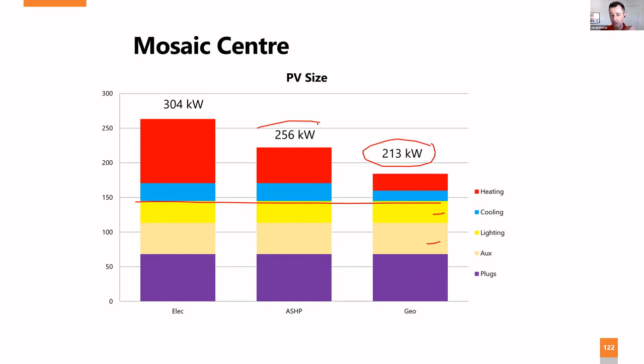And the cost of that solar PV is different. So even though the cost of the geo system was an $80,000 premium, we would save almost $300,000 over electric space heating and $130,000 over air source heat pumps, which again wouldn't be practical. And we didn't actually have enough room on the roof to fit this amount of PV. So not only is the geosystem the only way you would get to net zero on this site, it's the cheapest way to get to net zero.